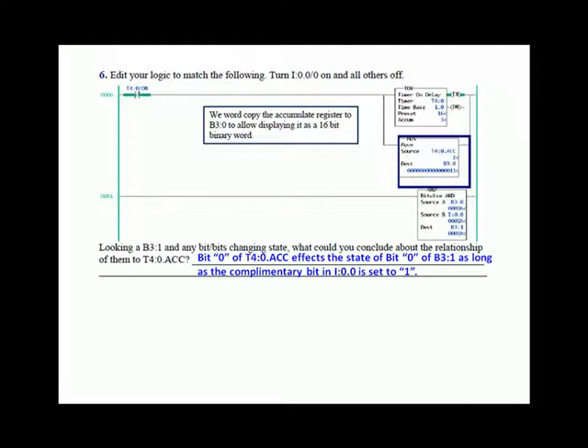Bit 0 of T4:0 accumulate affects the state of bit 0 of B3:1 as long as the complementary bit in I:0/0 is set to 1. B3:0 is going to constantly change — 1, 2, 3, 4 — and you'll just see the bit pattern increment across. Bit 0 is going to go on and off every other second, so every 2 seconds it will be 1 for 1 second and off for 1 second. So if you had input 0 on, then B3:1 bit 0 would go on and off every other count.